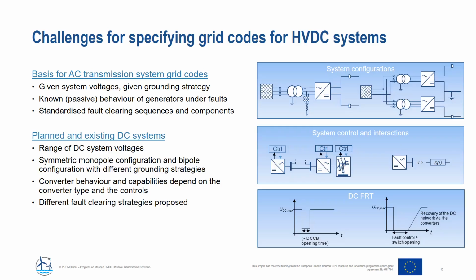When looking at the planned and existing DC systems, there's a range of DC system voltages applied. There are different configurations, so for example, symmetric monopole configuration and the bipole configuration would go along with different grounding strategies, leading to different behavior under fault conditions. And then the converter behavior and capabilities depend on the converter type and the associated controls. Overall, there's a lot of control systems involved, for example, also in the offshore wind farm, and there have been several interactions identified between those systems.